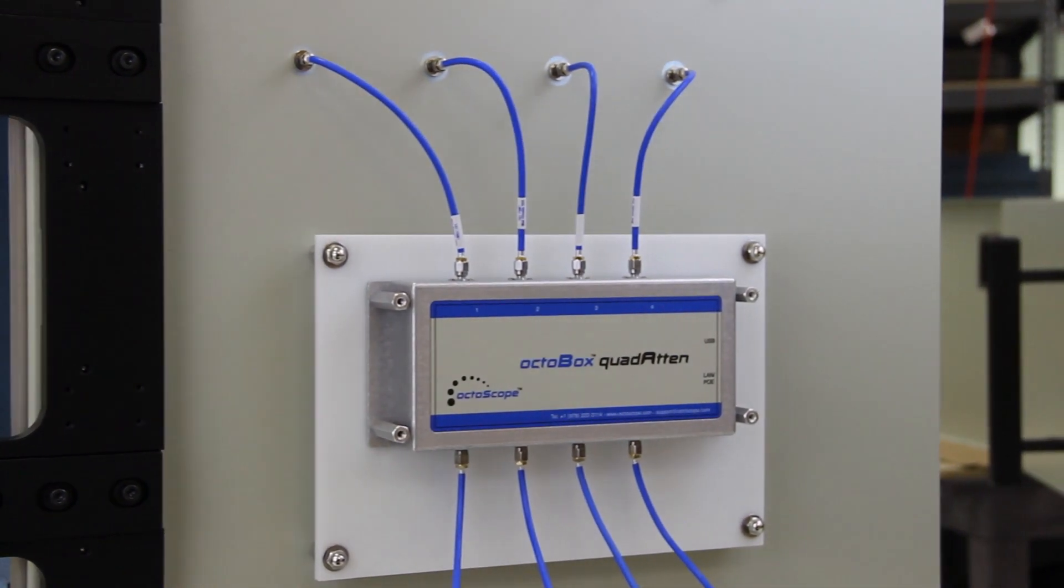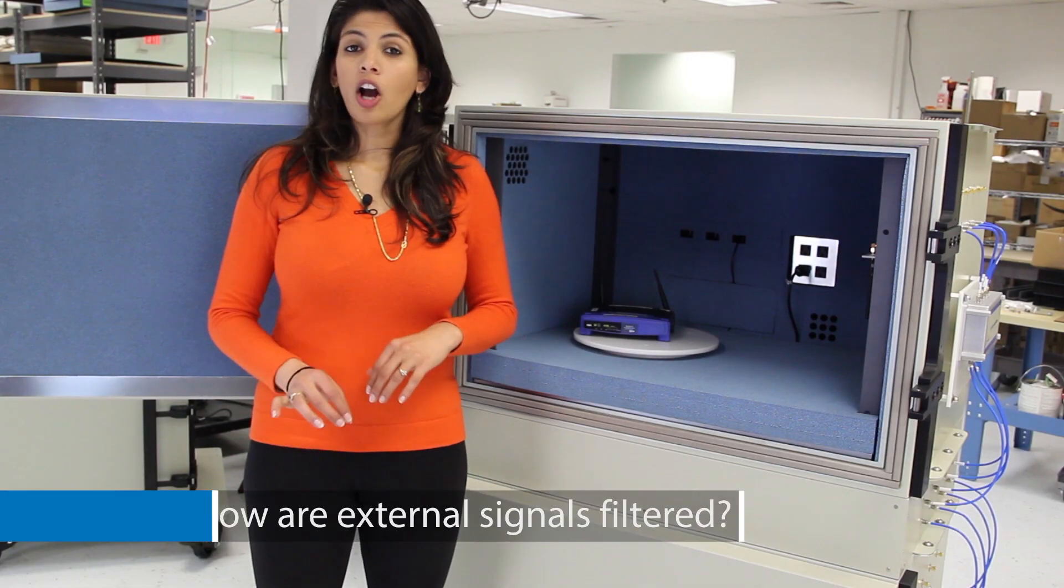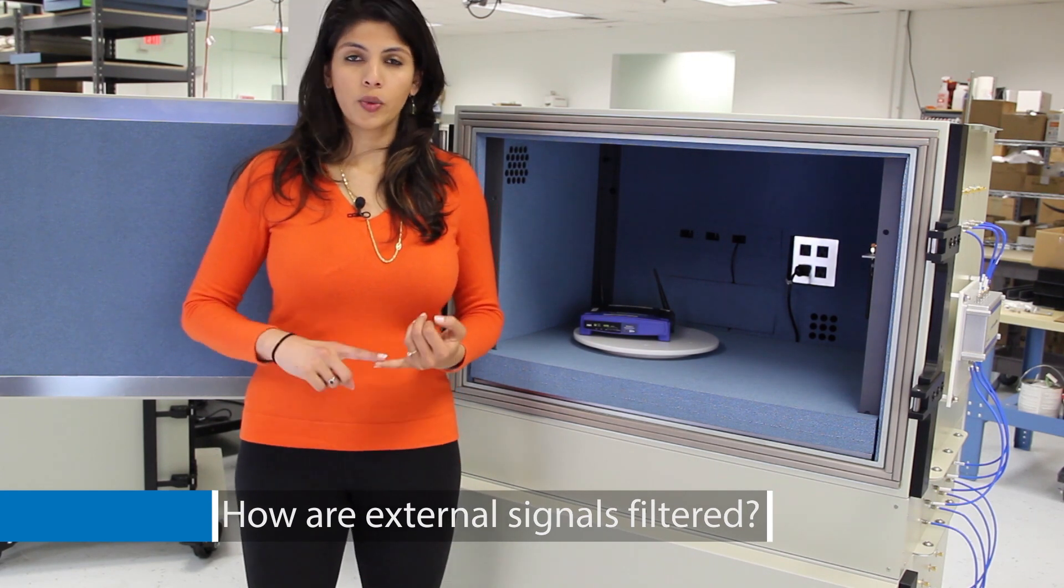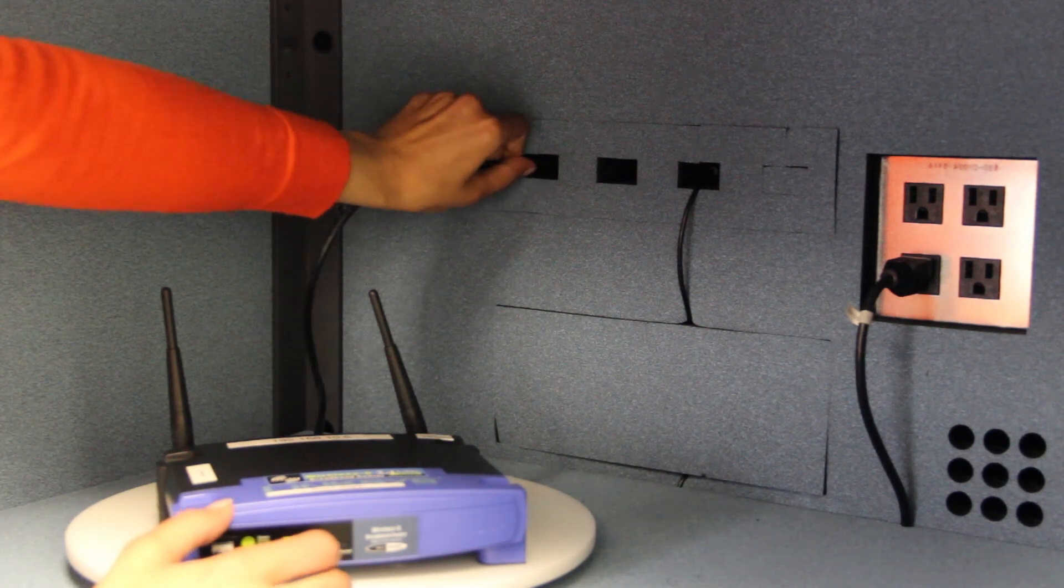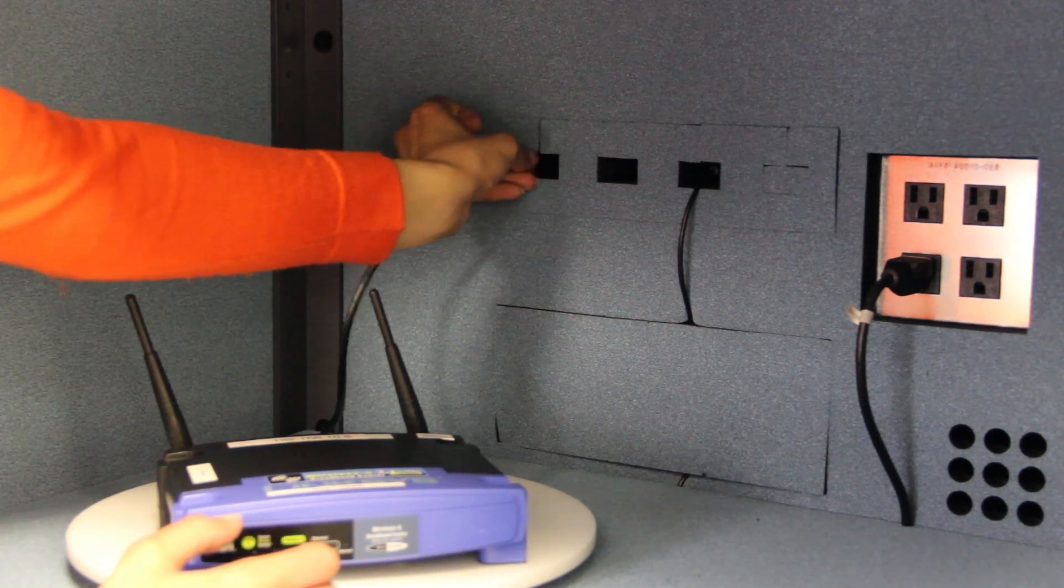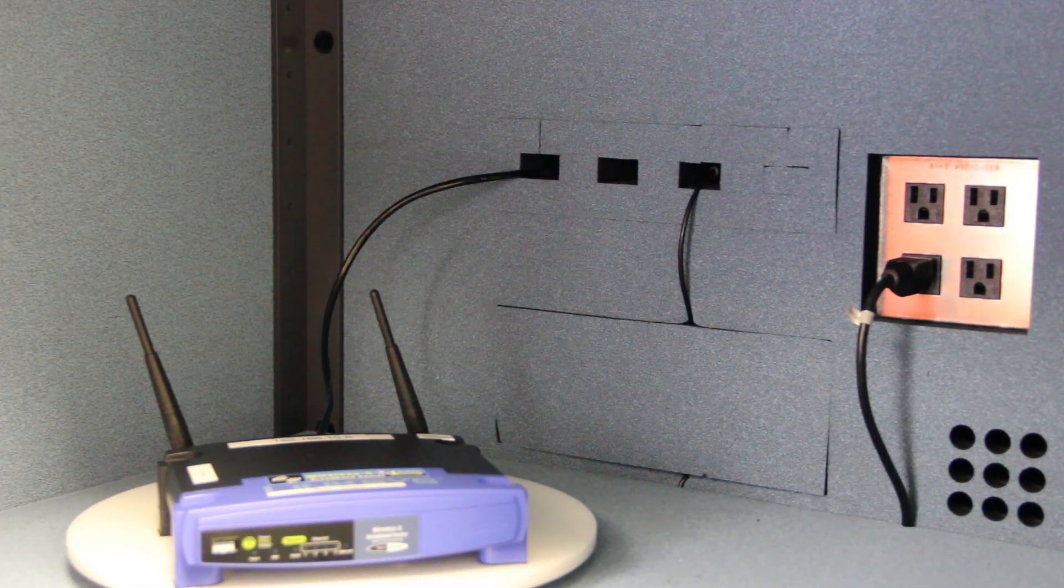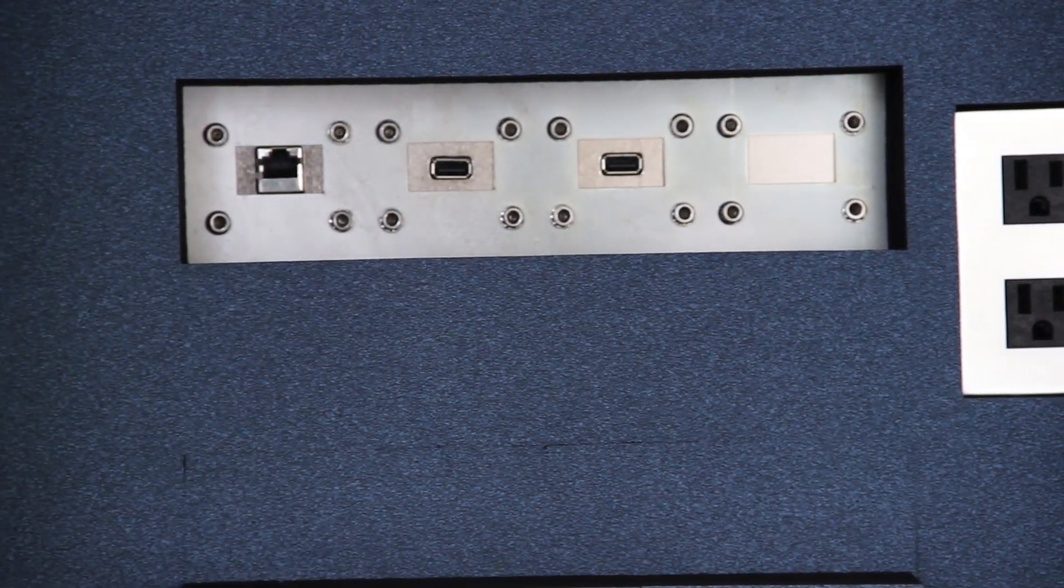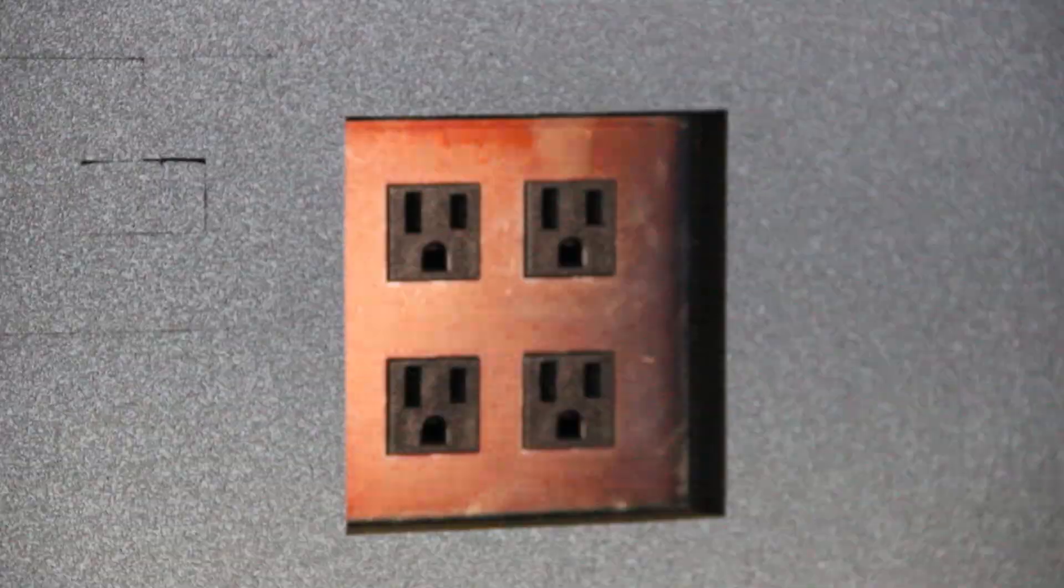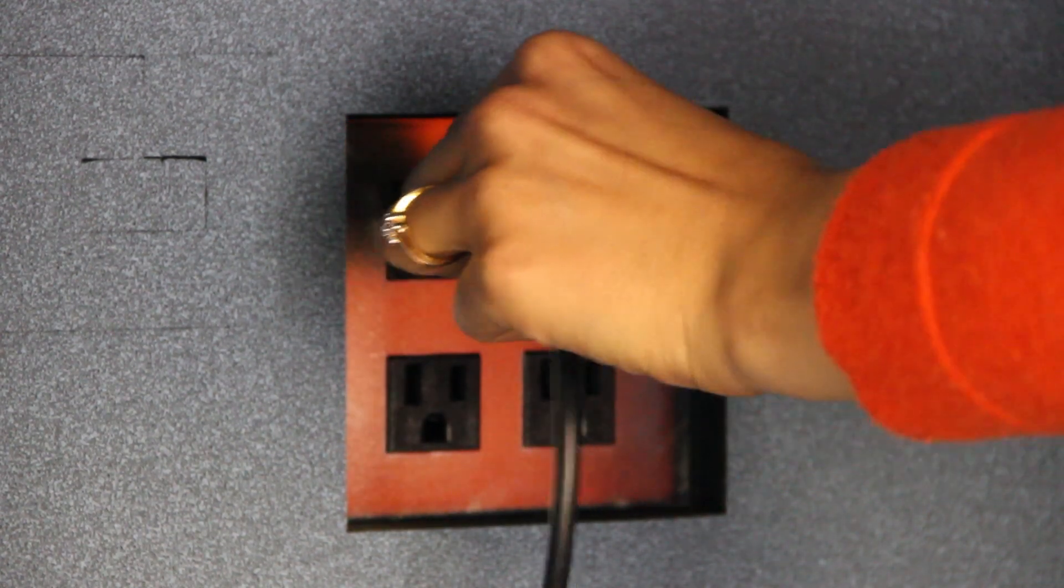Any copper wires such as USB, Ethernet, HDMI, etc. can act as antennas coupling interference between the outside and the test environment. Any copper cables entering the Octabox enter through filters. Power and ventilation are also filtered.